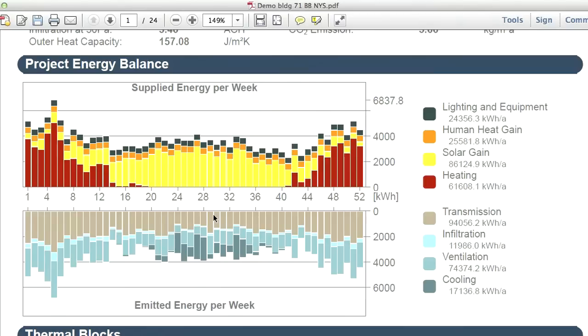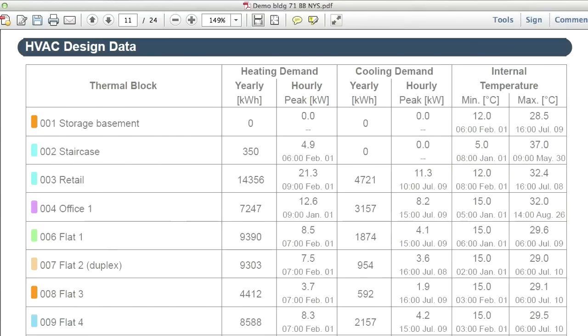The purpose of evaluating the baseline design with all systems set to 'not yet specified' is to obtain the annual load and peak load data necessary for baseline building system sizing. The HVAC design data chapter of the baseline design's energy performance evaluation report provides the crucial information about both annual and hourly peak heating and cooling demands of the baseline building.